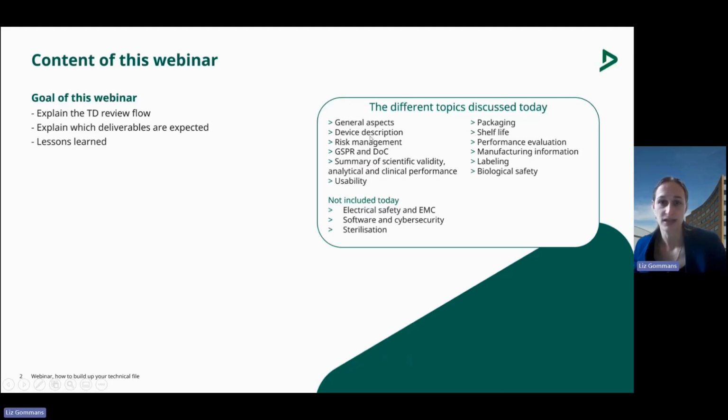So we have general aspects, device description, risk management, GSPR and declaration of conformity, summary of scientific validity, analytical and clinical performance is a big chapter, usability, packaging, shelf life, performance evaluation, manufacturing information, labeling and biological safety. What I will not talk about today are the electrical safety, software and cybersecurity, and sterilization. These are such big topics.